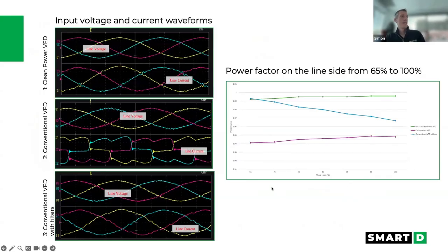So here you can see that in your middle screen, you have your standard 6-pulse without any filtering. And you can clearly see the current draw is non-linear, and that's the cause of your harmonics. If you're putting your passive harmonic filter at the bottom, you're back to having sine waves, but you can see at the top with the clean power VFD that you have these sine waves in both voltage and current without any filter integrated. You're also seeing a better power factor, that's in green at the top. You have almost unity power factor maintained by the clean power VFD without any filter.